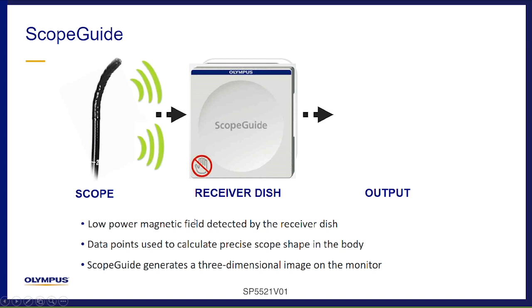So this is a little pictorial of how the ScopeGuide works with the receiver dish and the sensor. The scope emits these low-power magnetic fields detected by the receiver dish. The signal is picked up by that receiver dish. Data points are then used to calculate precise scope shape in the body. ScopeGuide generates a three-dimensional image on the monitor.